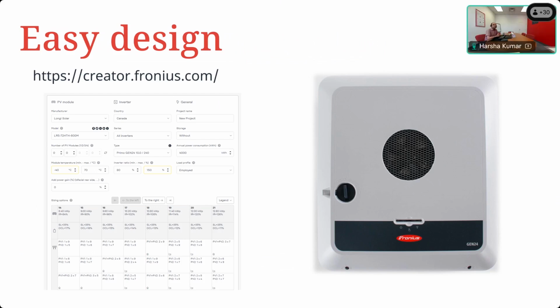So for example, here you can look at this example on the tool that you see here. There's this little field called inverter ratio. The default on it, if you were to just load the tool without having plugged in anything, is 80 and 120. I've changed it to 150. So all the changes that I've made here, like for example, I've set the temperature to -40, it's highlighted in yellow. You can see that. And on the high side, the inverter ratio is set to 150%, and the bifacial gain is set to 0. Now, if I include the bifacial gain based on whatever percent you expect, depending on what your albedo is and how they prepared the surface behind the PV array, then you can plug those numbers in there, and you will see that that is taken into account within the 150%.